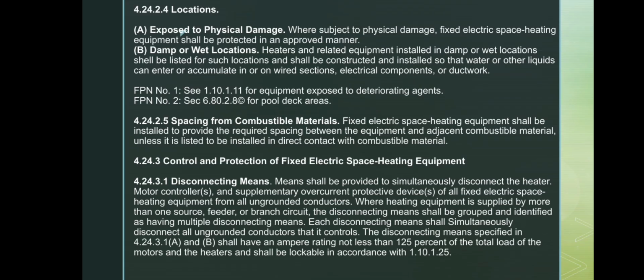Disconnecting means: there must be a way to simultaneously disconnect the heaters, motor controller, and any supplementary overcurrent device from all ungrounded conductors. If the equipment is supplied by multiple sources, the disconnects must be grouped and clearly identified. The disconnecting means must be rated at 125% of the total load and must be lockable.